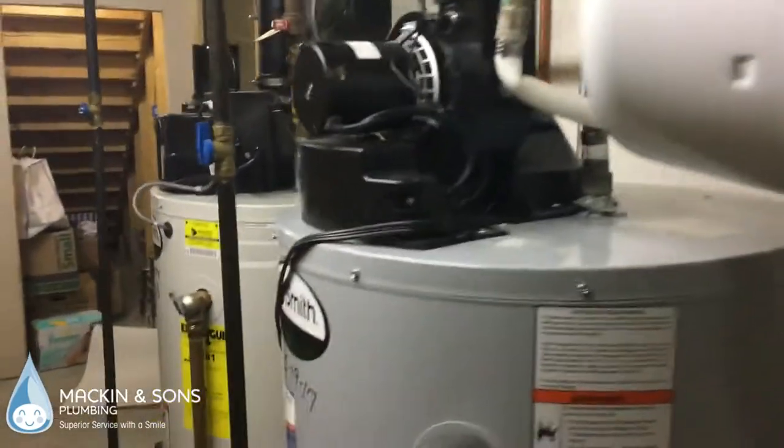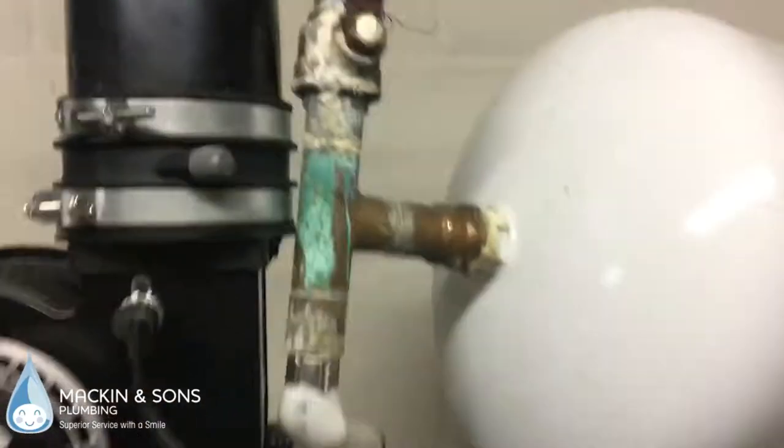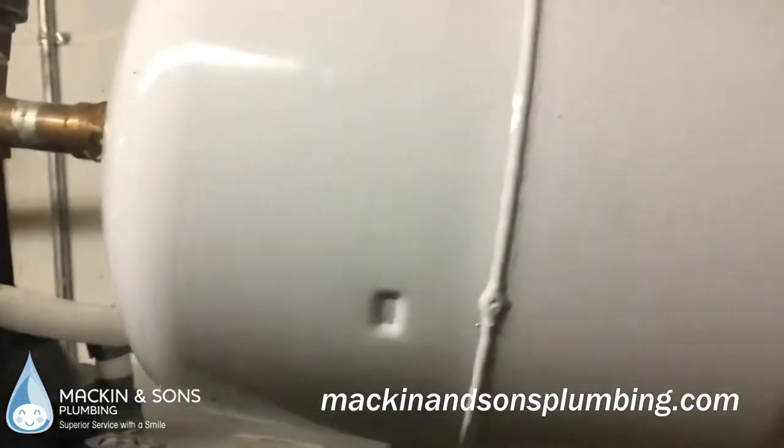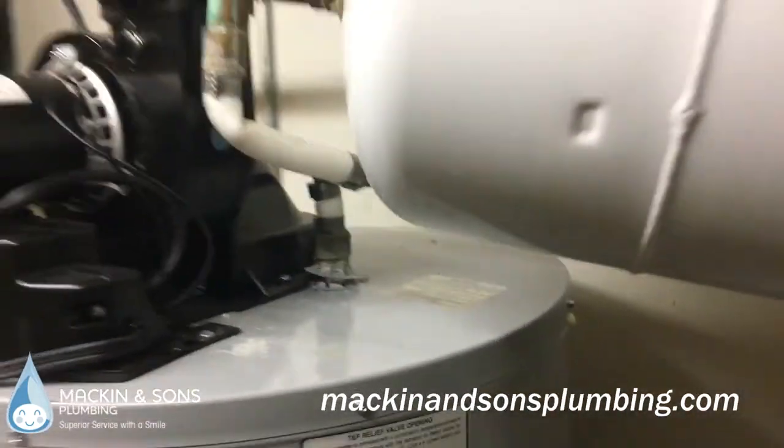We got called in to look at a water heater that was leaking. The heater on the left is leaking — no big deal — but then we noticed this: it's unbelievable. This is an expansion tank that is full of water, which is not normal, but they put it in with plastic pipe and there was nothing supporting it.